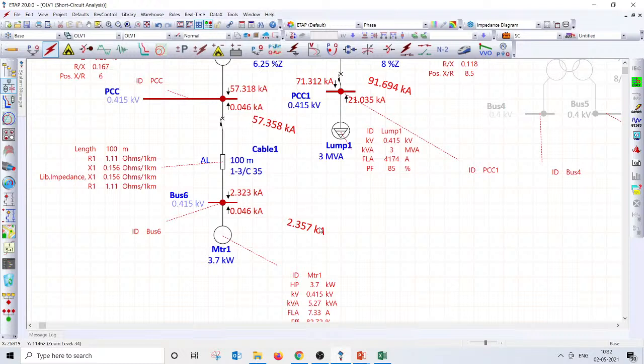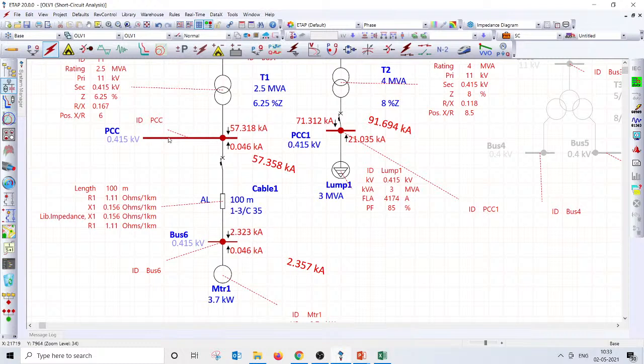So why should a 3.7 kilowatt motor not be connected at PCC? PCC is rated for a short circuit current of 65 kiloamps or 50 kiloamps, depending upon the transformer rating and transformer impedance. And connecting a small MCCB of just 10 amps, you need to force that MCCB to be rated 65 kiloamps or 75 kiloamps based on the short circuit current. That's point number one. And you can understand that the fault current variation is huge when the length of the cable is really far, and if I had originally modeled the 4 square cable, the fault current could be too less, right?